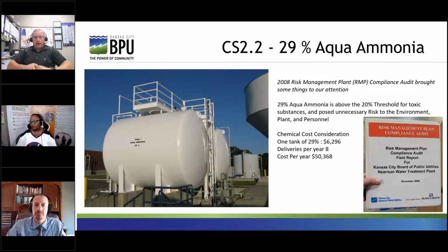Case study 2.2. The plant was designed for use with 29% aqua ammonia. And from 2008, roughly, we used the 29% concentration. In 2008, a risk management plan compliance audit brought some things to our attention. 29% aqua ammonia is above the EPA's 20% threshold for toxic substances and posed unnecessary risk to the environment, plant, and personnel.